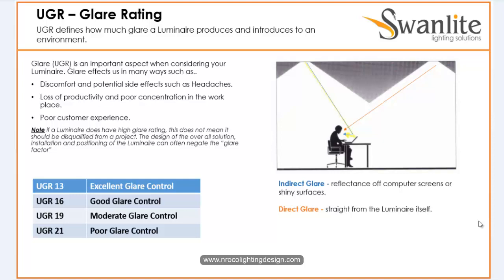If the luminaire you selected for your project is very glary — for example it has a glare value of 25 or 26 — you can still use it, but you need to adjust the location, the tilting, and maybe the height of the luminaire so you will get a good glare value.